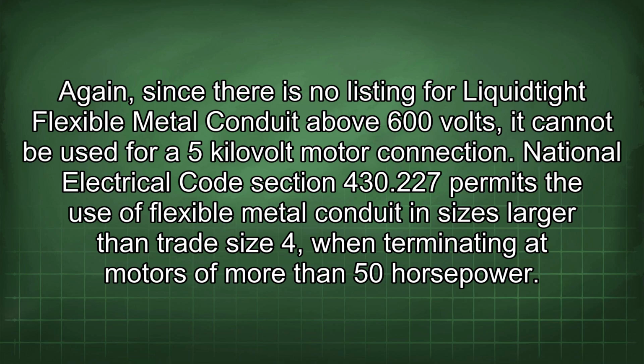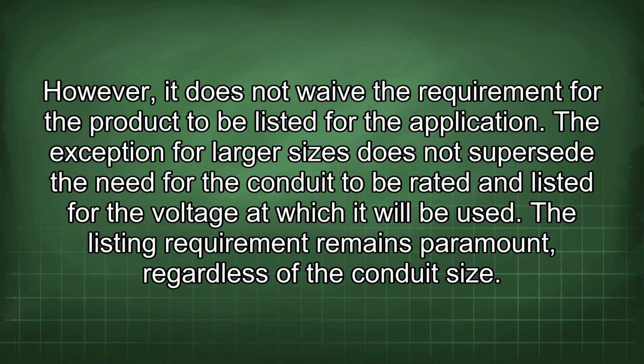National Electrical Code Section 430.227 permits the use of flexible metal conduit in sizes larger than trade size 4 when terminating at motors of more than 50 horsepower. However, it does not waive the requirement for the product to be listed for the application. The exception for larger sizes does not supersede the need for the conduit to be rated and listed for the voltage at which it will be used. The listing requirement remains paramount, regardless of the conduit size.